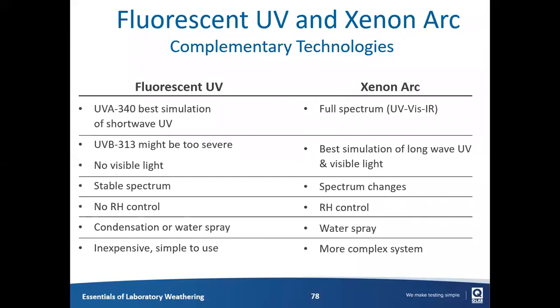Wrapping up the comparison between fluorescent UV and xenon arc: we consider these to be complementary technologies. One is not better than the other — they have different goals, and companies that do a lot of weathering testing will almost certainly have both devices. Fluorescent UV has the best simulation of short-wave UV with UVA-340 lamps; xenon arc's major advantage is that it reproduces the full spectrum — UV, visible, and IR. The spectrum doesn't change for fluorescent lamps but does for xenon. The Xe-2 and Xe-3 can control relative humidity; fluorescent devices can't — however, the fluorescent UV can produce condensation, which xenon arc testers cannot. Either one can be equipped with water spray, though it's much more common in xenon arc standards. The fluorescent UV does have some advantages in cost and maintenance.